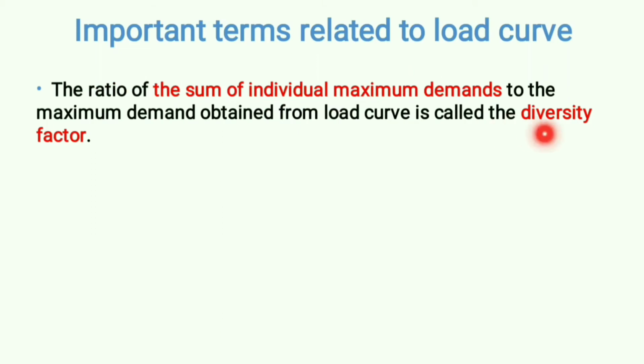Next we'll see what is diversity factor. The ratio of the sum of individual maximum demands to the maximum demand obtained from the load curve is called diversity factor. Let's understand this by an example.